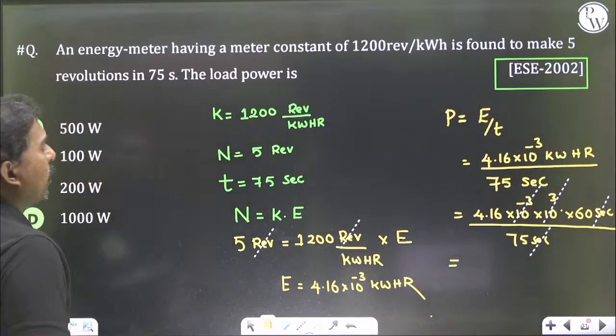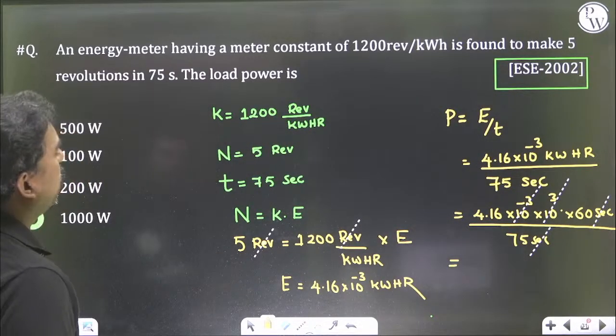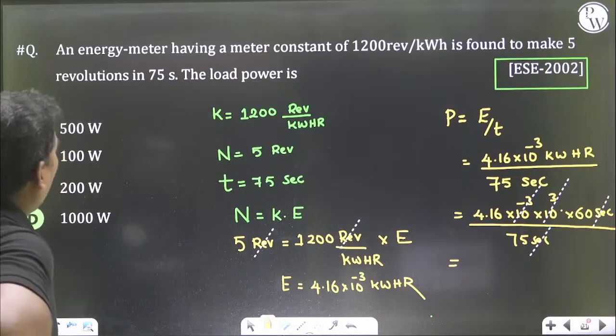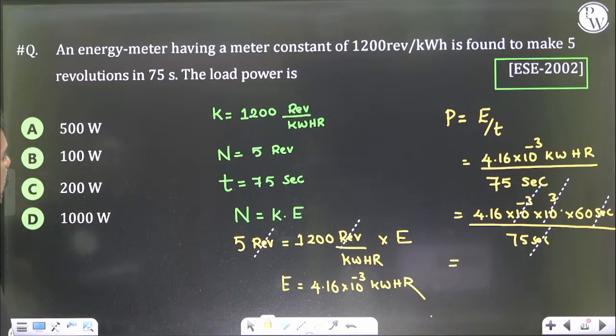Number of revolutions is proportional to energy. Meter constant is 1200 revolutions per kilowatt hour, found to make 5 revolutions in 75 seconds. Time is 75 seconds, power equals energy per time, N is proportional to energy, N equals K into E: 5 revolutions, 1200 revolutions per kilowatt hour.